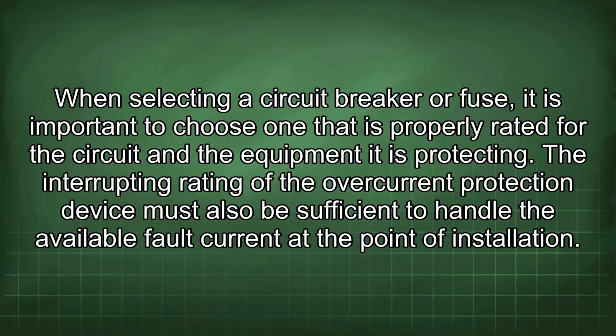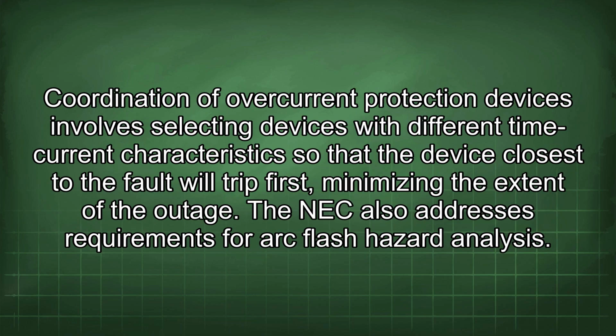The interrupting rating of the overcurrent protection device must also be sufficient to handle the available fault current at the point of installation. Coordination of overcurrent protection devices involves selecting devices with different time current characteristics so that the device closest to the fault will trip first, minimizing the extent of the outage.